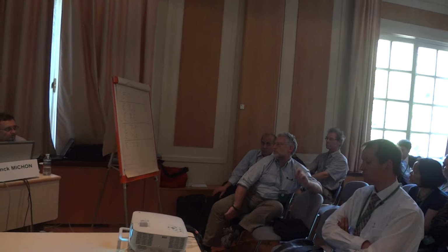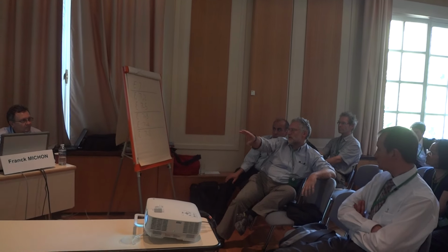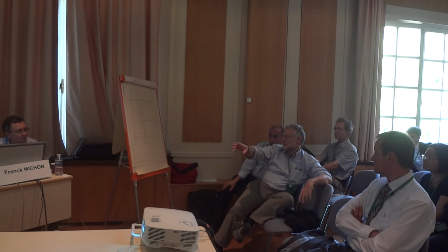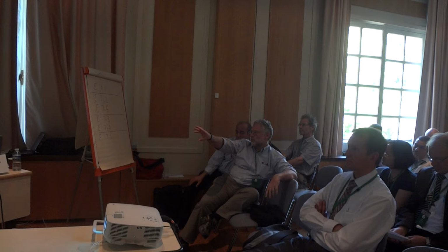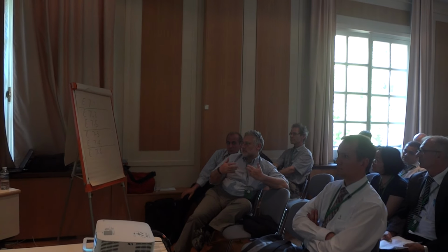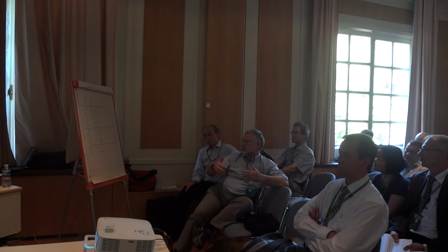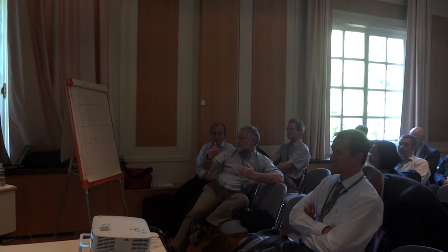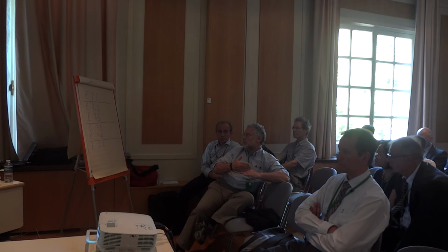Nigel? Yeah, I want to touch on where Fred was going there. I think one of the interesting things that you've done here with the image analysis is you've got very high stresses, but in very localized regions, and we know that paper, polyethylene, EPR, etc., have strength that increases as we get to very small sections.